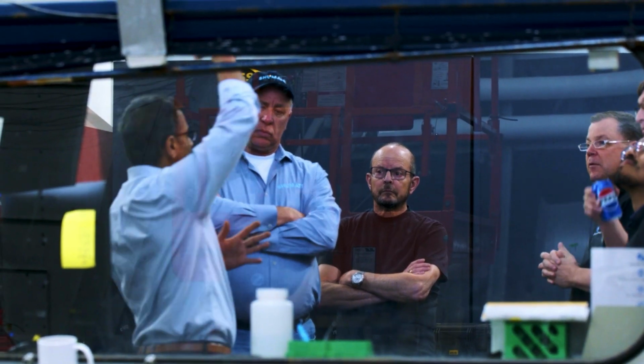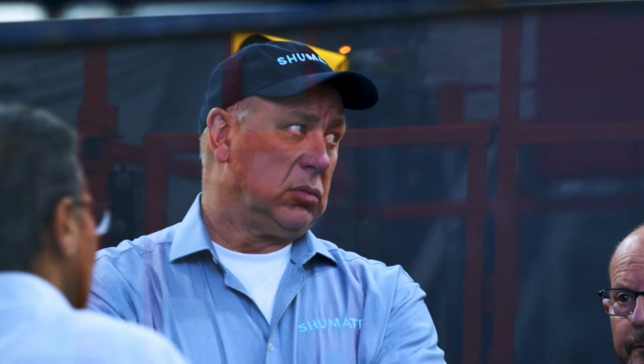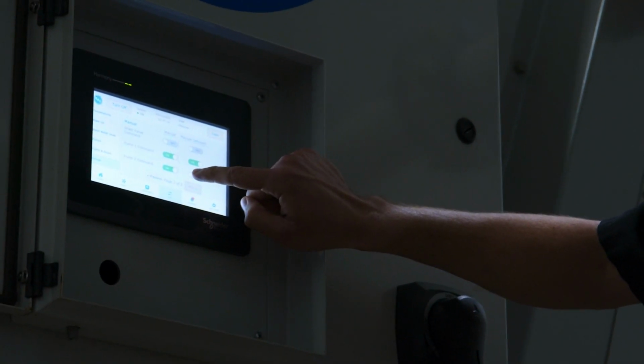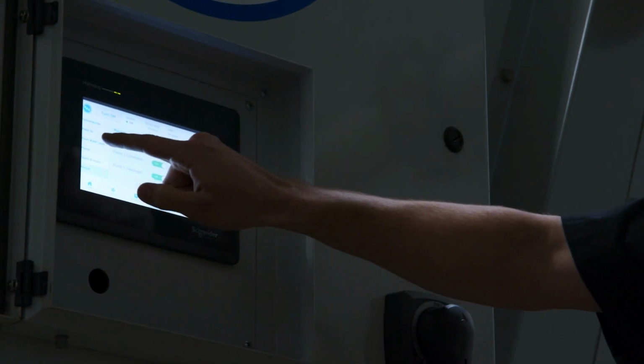Why does our design matter? Basically, our connected PUE is 1.2. So if you're building a gigawatt of power, you need 1.5 gigawatts of power to your site to incorporate the IT plus the mechanical. With our design, that's 1.2 gigawatts. Well, what does that mean? That's 300 megawatts of generation that you don't need.